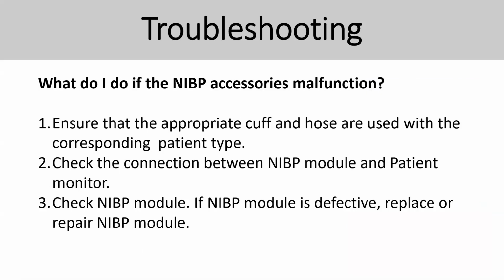Okay, what do I do if the NIBP accessory is malfunctioning? Normally you ensure the cuff and the hose are used correctly with the patient, and check the connection between the NIBP module and the patient monitor. Check the NIBP module. If the module is defective, replace or repair the NIBP module. To check the NIBP module, if you have the same model, maybe you can cross-exchange and test it out.